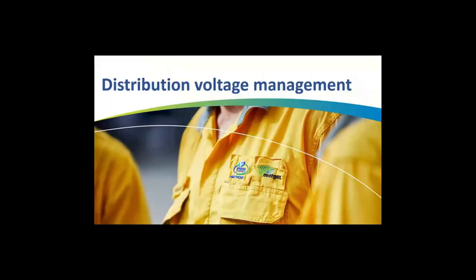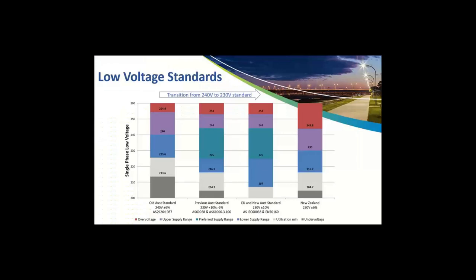In terms of distribution voltage management, we've recently undergone a transition. We've traditionally had a 240 volt system, similar to the UK, and we've been transitioning across to the 230 volt system, which is aligned with now the IEC European standards. And that's seen limited reductions in the upper limits, but significant reductions in the lower limits on voltage. And so that's allowed us to lower voltages to accommodate voltage rise during reverse flows. And that's been valuable for increasing voltage capacity.